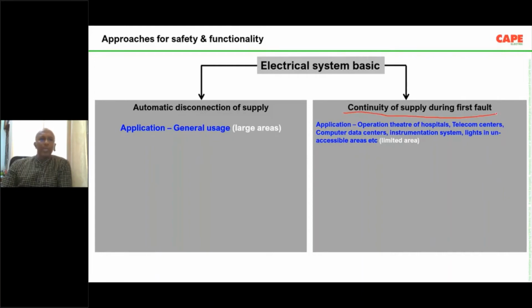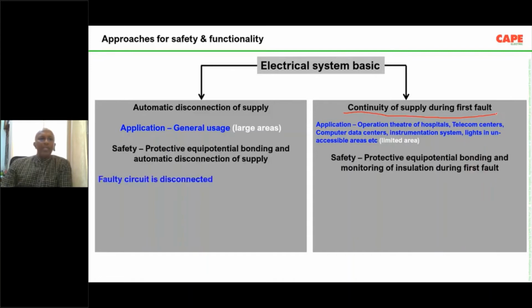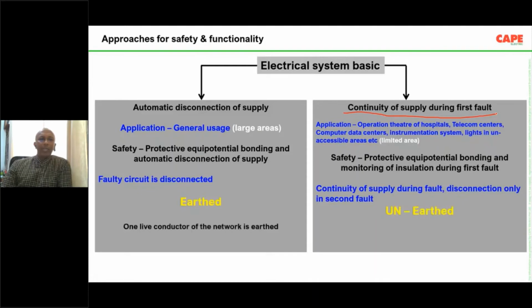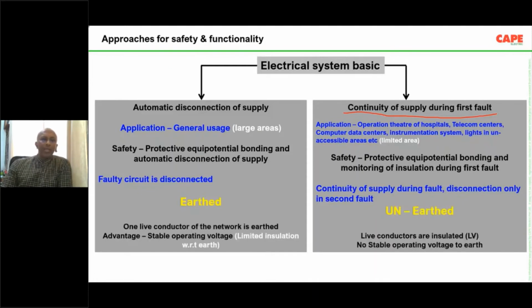There are two approaches, and in the first case, safety is achieved by protective equipotential bonding. I won't explain much. The first one is called earthed supply, and the second one is called unearthed supply. People in the hospital sector know IT supply, especially for the operation theater or certain activities. Unearthed supply is also used. There is an isolation transformer. The secondary side of the isolation transformer is not earthed, and there, insulation monitors are used, and you achieve a safety measure called continuity of supply during first fault. So these two are the basic concepts.